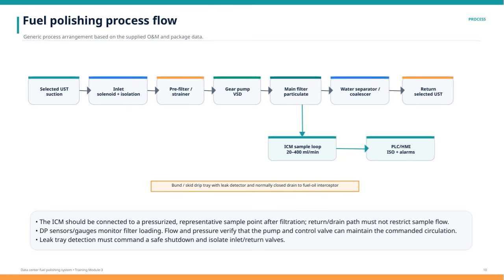If a leak is detected, this setup triggers a safe shutdown and isolates the inlet and return valves to prevent spillage or contamination. Differential pressure sensors and gauges continuously monitor filter loading, while flow and pressure readings verify that the pump and control valve maintain proper circulation. Overall, this system ensures fuel is continuously cleaned, monitored, and safely handled to protect both equipment and the environment.